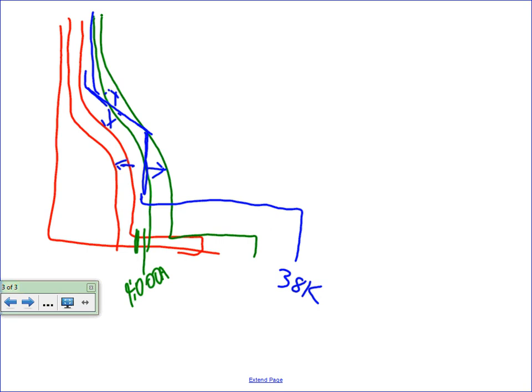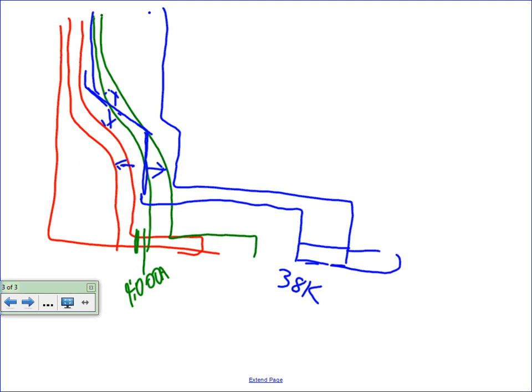Now you got maybe a service breaker that's rated at 2,000 amps. We use that same type of breaker, a solid state breaker, but it's way over here. And we just adjust it to make sure that its curve doesn't overlap with the one in front of it. And you're still going to get a tail on the solid state breakers. But anything above this point, that breaker is going to trip. And anywhere above this point, that breaker is going to trip. But now, at least we're coordinated to wherever this is, which might be 56K or 65K or whatever the override is built into that breaker by turning the instantaneous on.